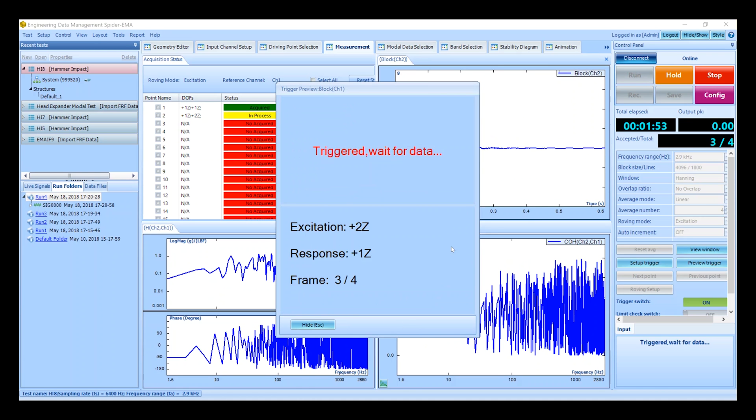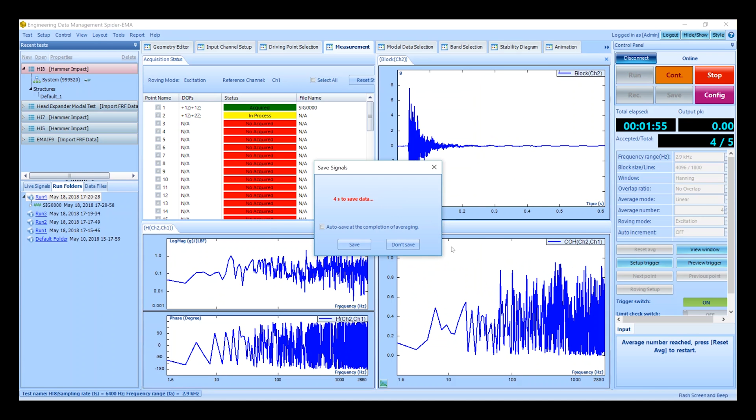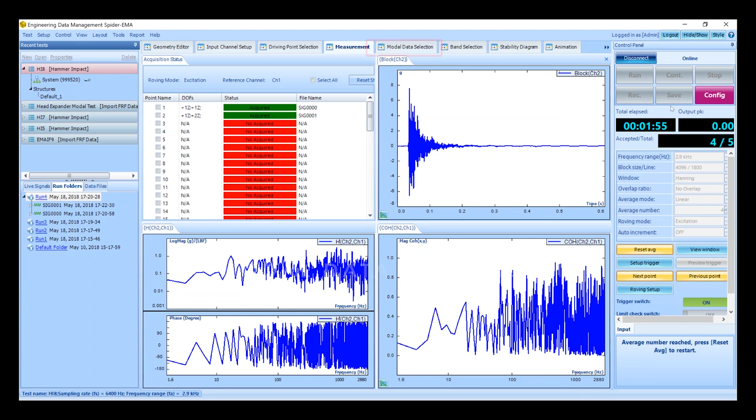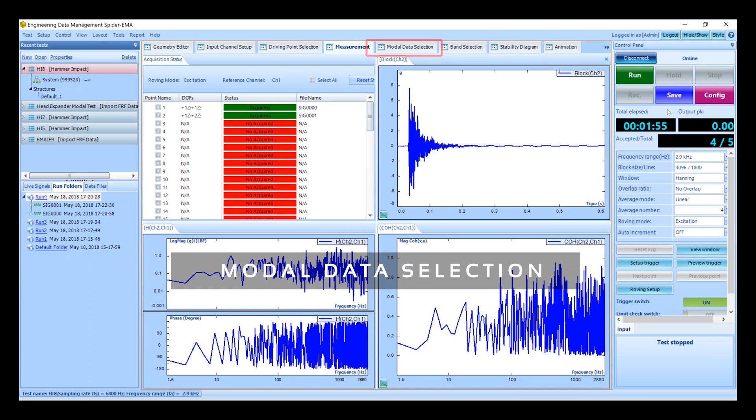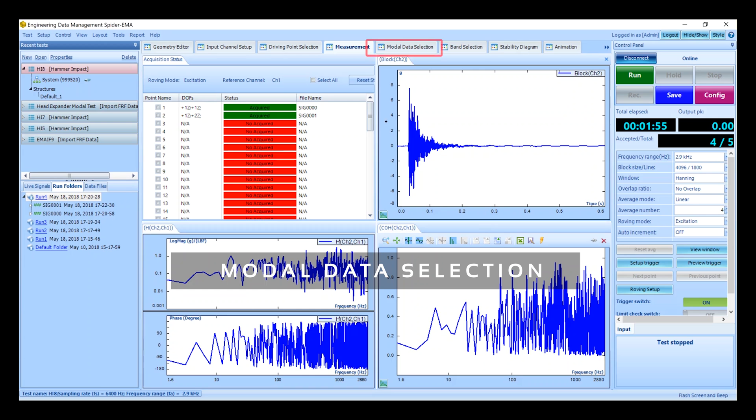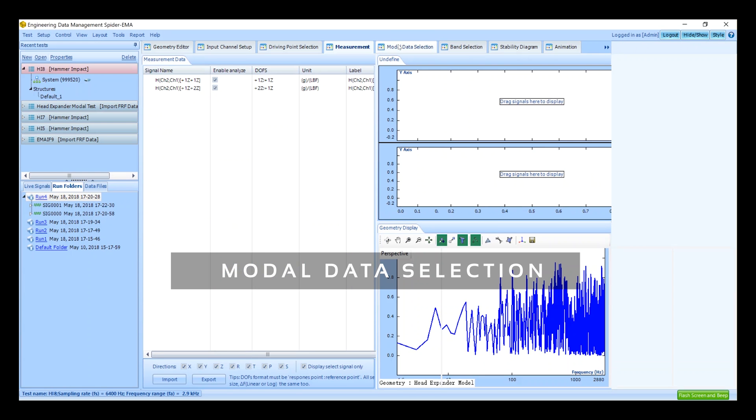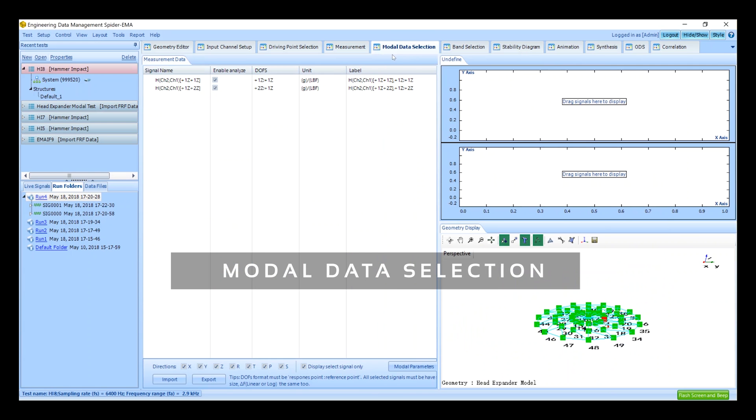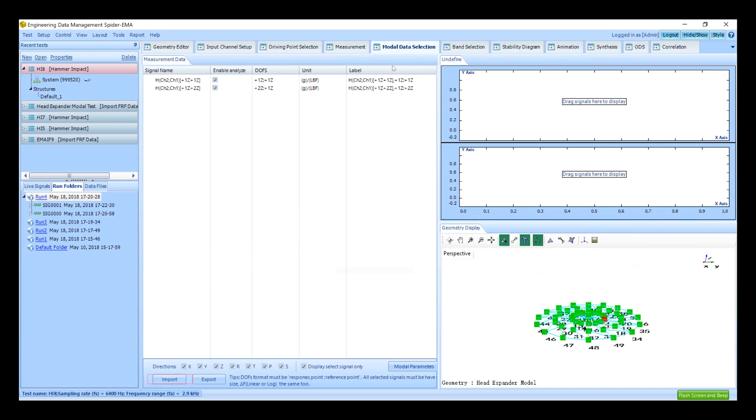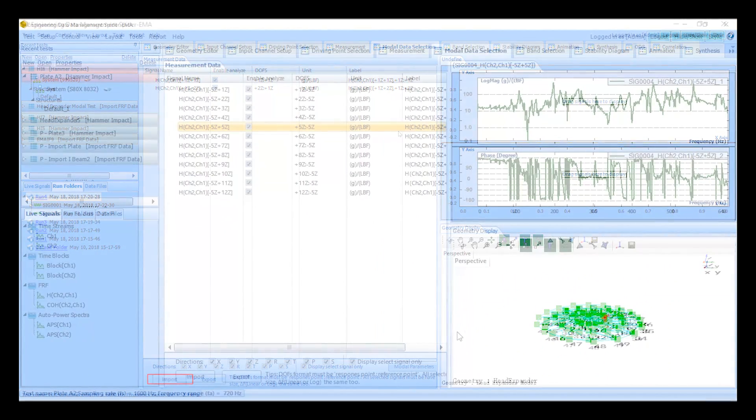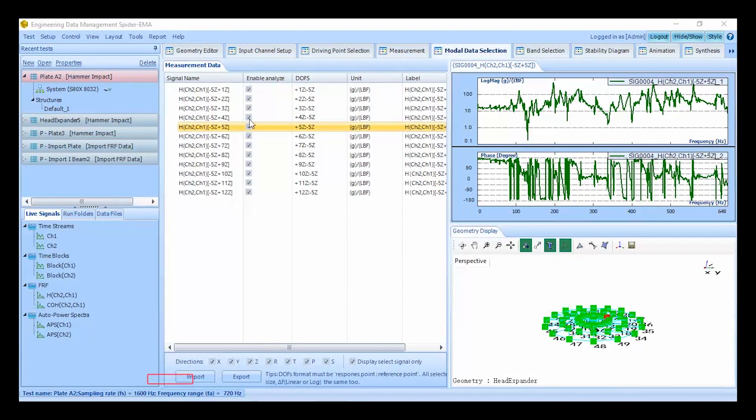Once all the points have been measured we can start reviewing our acquired modal data. Click on the modal data selection tab. The modal data selection tab is where we manage our testing data. This list shows all the FRF measurements that were acquired during the test.